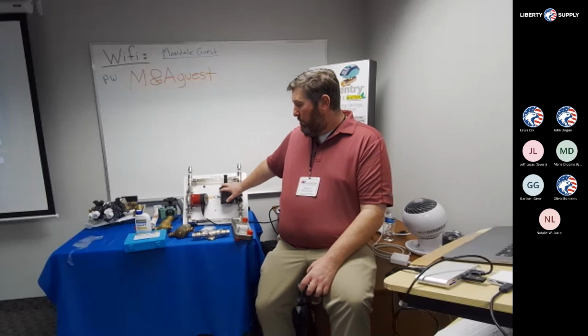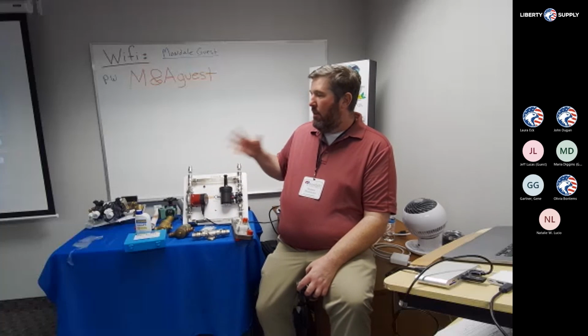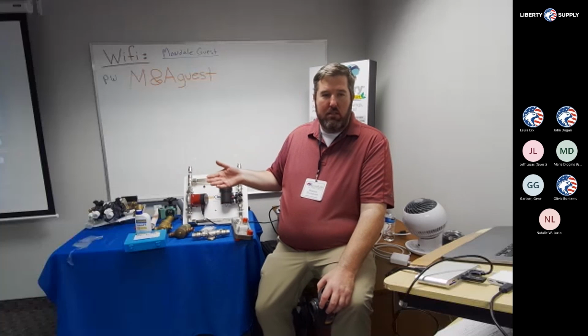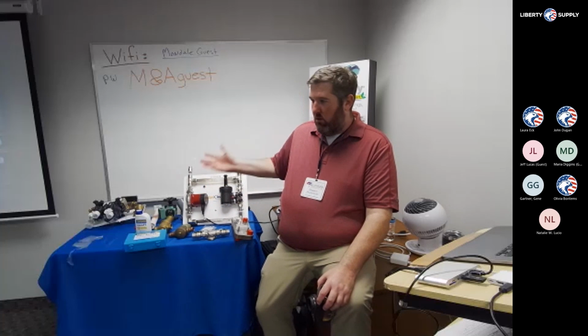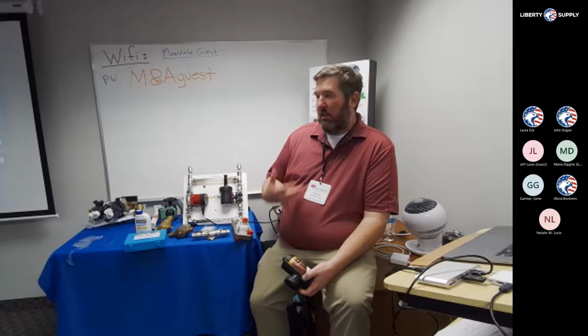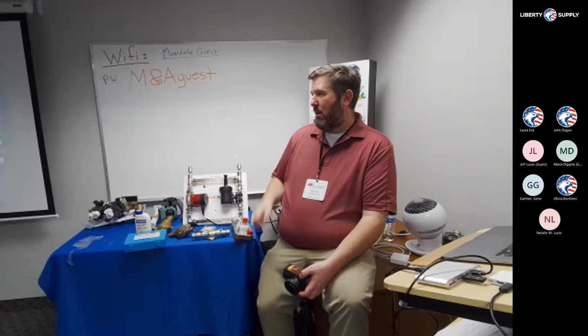But if you have a straight radiant floor system, we don't have a lot of the iron oxide to deal with. Maybe we're just dealing with the chemical side of it. So there's different paths. That's why every job that we look at or get called about, we kind of ask the questions and try to come up with a solution that makes the most sense. Obviously, there's all different jobs that have all different problems. Sometimes I get samples back that it's strictly a sediment problem. So we just need to get some kind of water filter in there to kind of get the sediment out, whether it's temporary or a permanent filter. We need some way to get that sediment out of the system because the pH and the hardness is fine, but that's just the only issue.